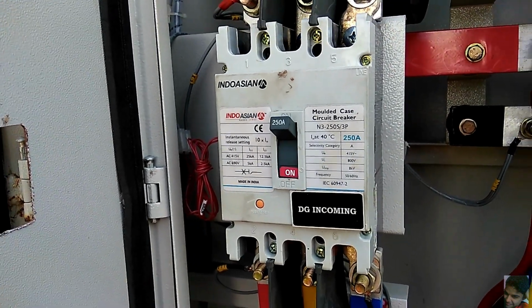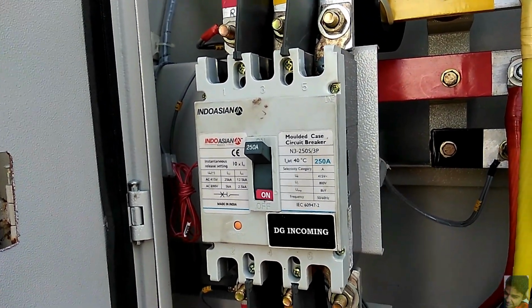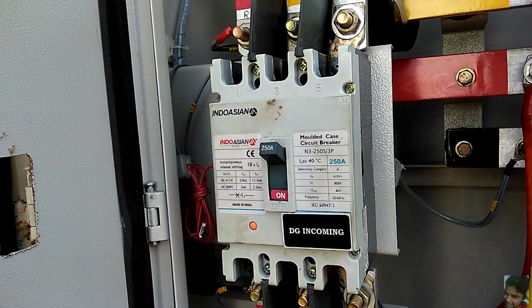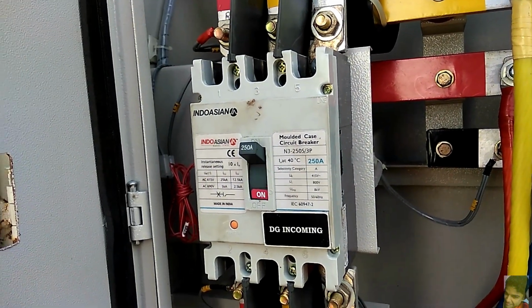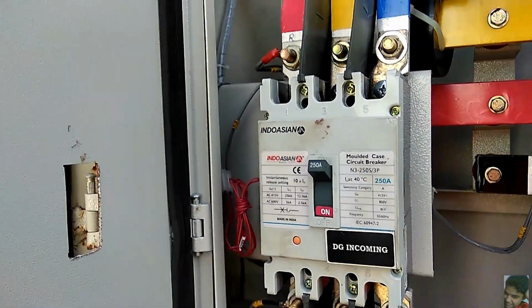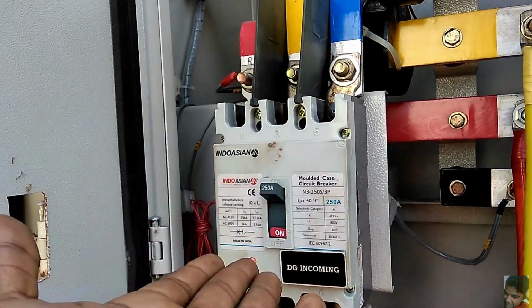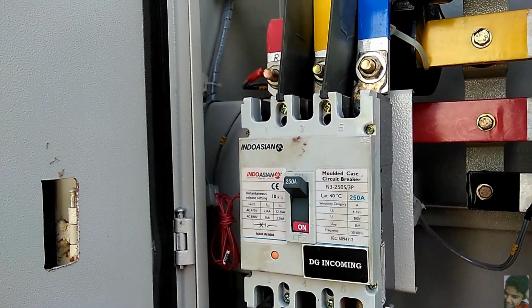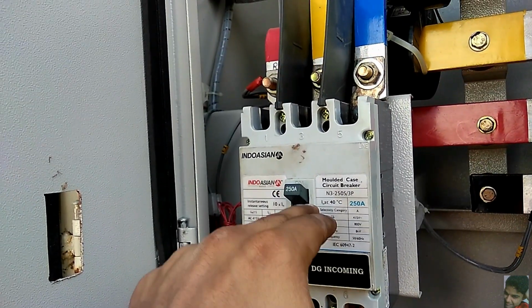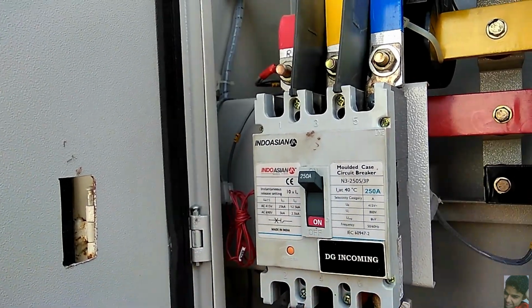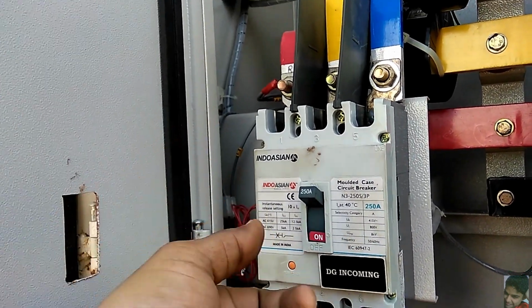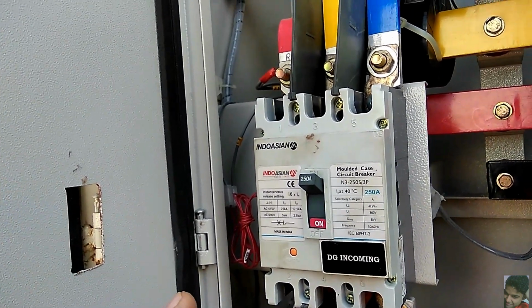So ideally in those cases, you must first see what has caused the trip, to figure out whether it's a problem. It could be a short circuit, in which case if you try to start it again, then maybe this can fail, and then it will not be protecting your system. When it is in trip condition, the breaker is down, you cannot switch it on directly, because when you switch it on, there's a spring inside, it will prevent it from starting.